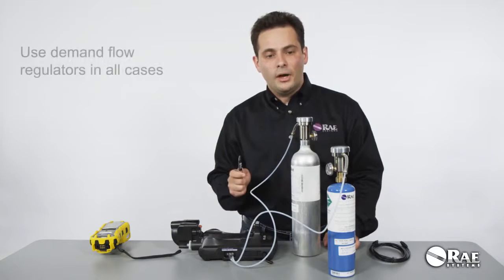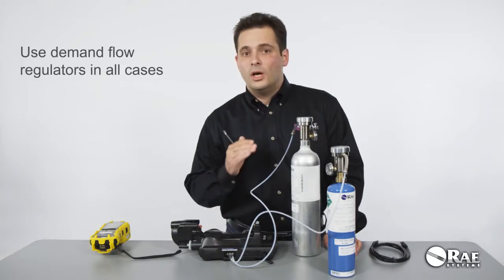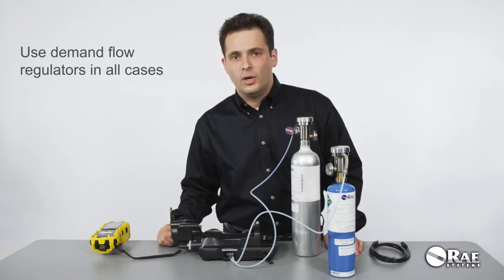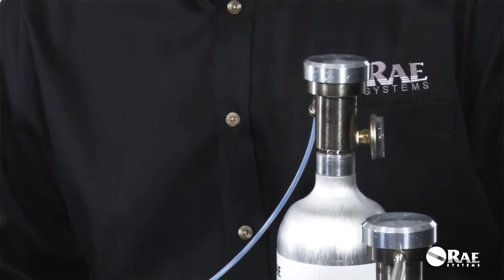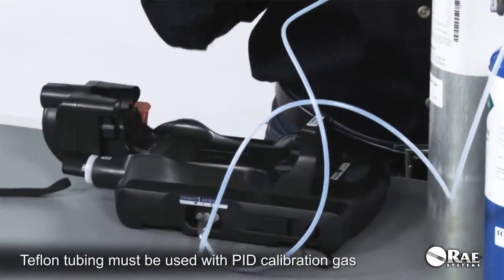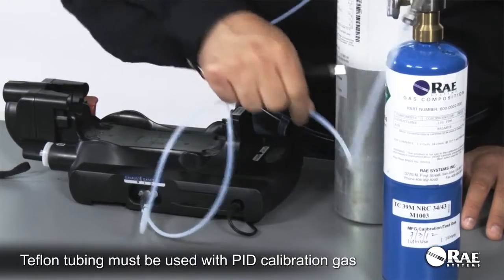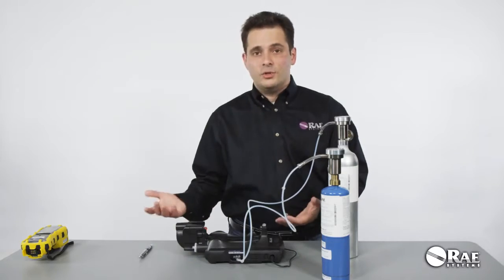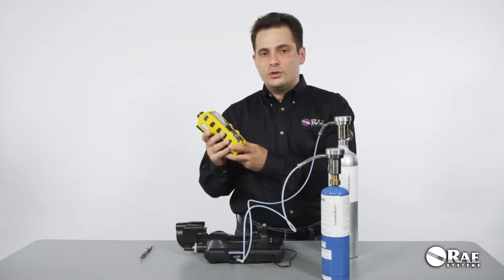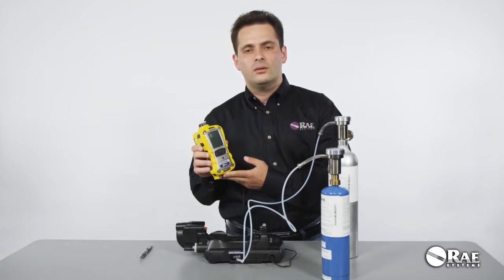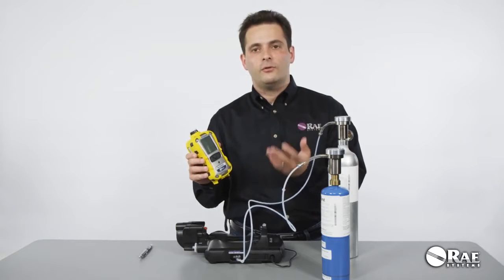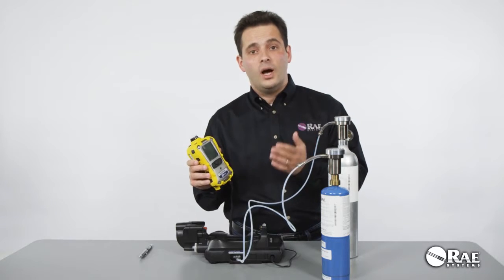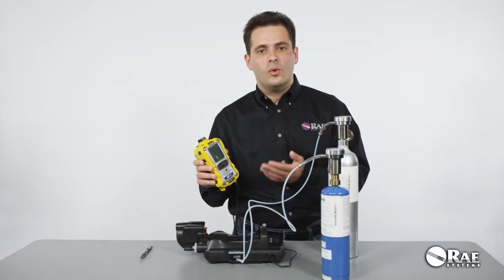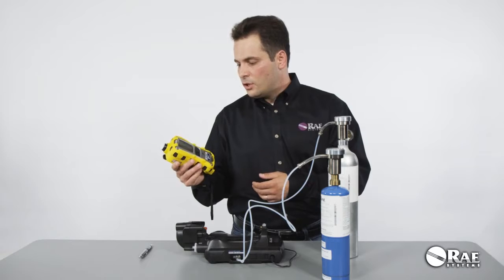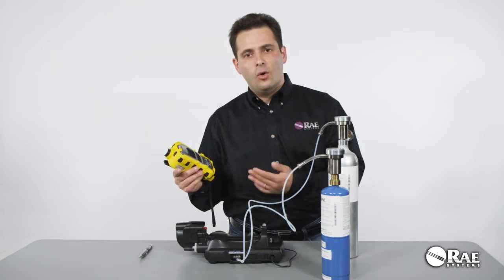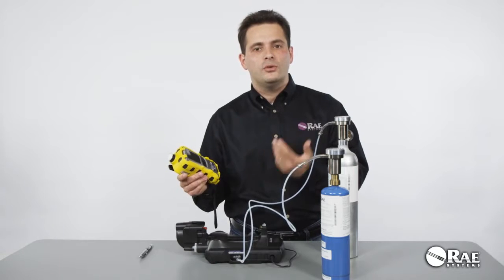Please note that it is required that demand flow regulators be used in all cases whenever you're using the AutoRAE 2, regardless of the AutoRAE 2 configuration. We always require that whenever you use a gas to calibrate the PID sensor, you use Teflon tubing with that gas. So now the system is ready for use. All you need to do is make sure that your MultiRAE has compatible firmware in it so that it can be recognized by the AutoRAE 2, and that firmware is application firmware version 1.10 or higher and sensor firmware 1.03 or higher. And then your MultiRAE needs to be either turned off or it needs to be turned on and put into the AutoRAE 2 communications mode.